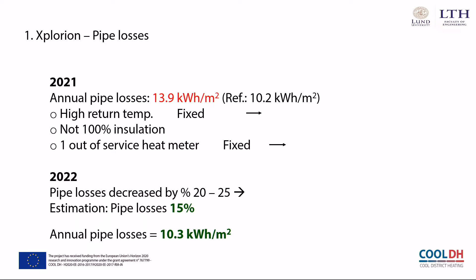The second reason was that not all of the pipes are insulated completely. And the third reason was that one of heat meter was out of service, that it also was fixed. So by solving these problems, in this year, according to our calculations, pipe losses decreased by around 25%. And so our estimation is that pipe losses will decrease to 15%, from 21 to 15%. And annual pipe losses could be 10.3 kilowatt hour per square meter, really close to reference value, or even could be lower than this value.